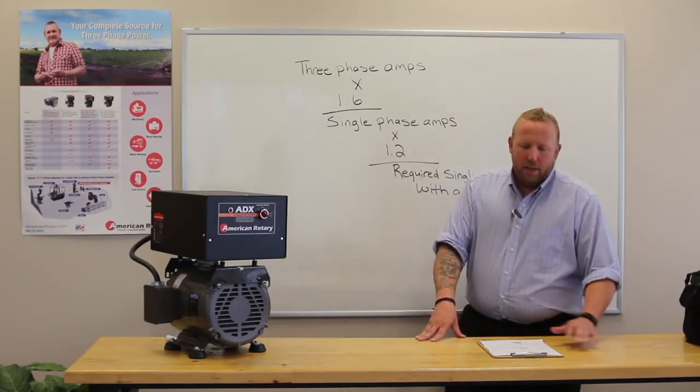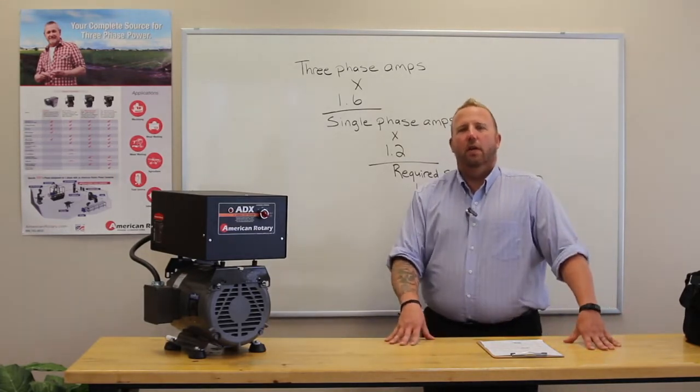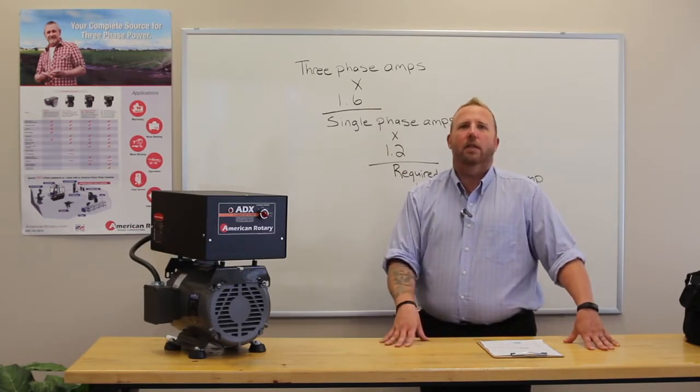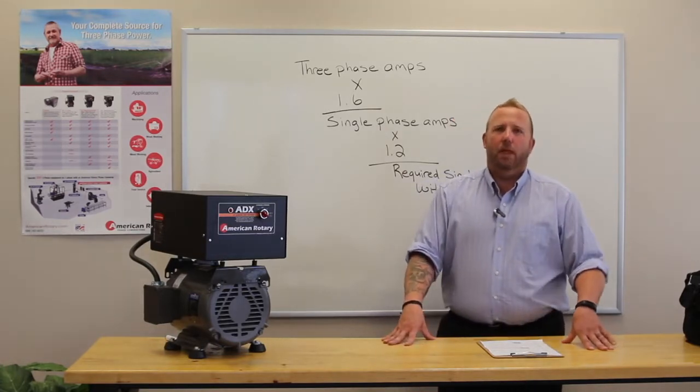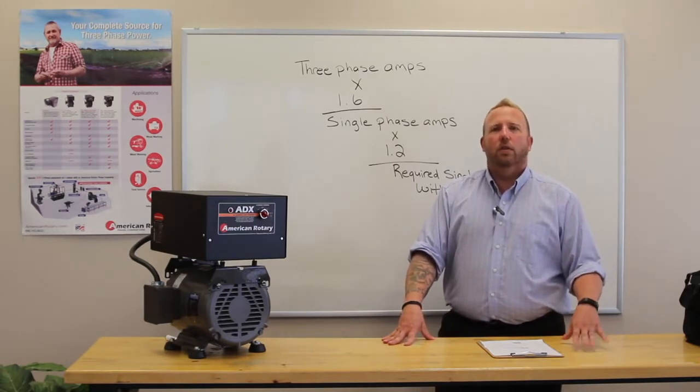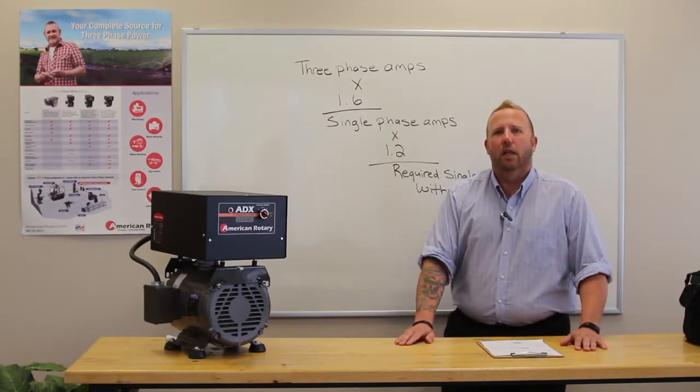Number three, the size of your load. When you call in asking about a phase converter, we're going to need you to tell us your horsepower, your amps, your kilowatts, so that we can calculate what would be the best phase converter for you. As a rule of thumb, you want to go two to one. So two times the size of your load will give you the size of the phase converter that you're going to need.